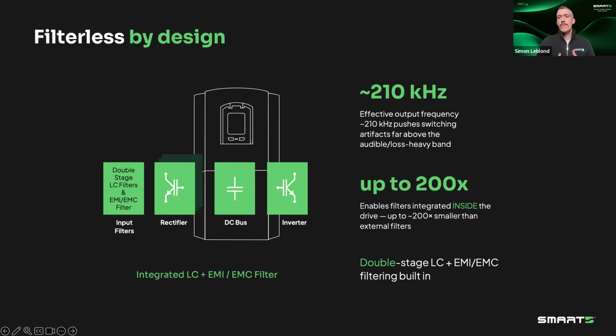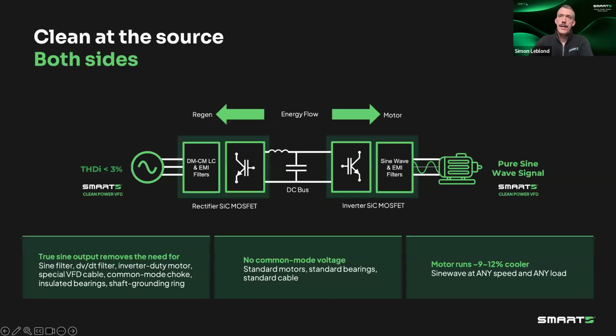So from your perspective, you're getting a self-contained drive enclosure with no filter cabinet outside. Filterless is the shorthand here because in effect, we do have filters, but they're just integrated in the product. And from your perspective, when you're specifying, you don't need to consider them. And that's really a symmetrical architecture. So on both sides, we have those integrated filters with that technology: double stage filters and EMI filters on the grid, and sine wave and EMI filters on the motor side.